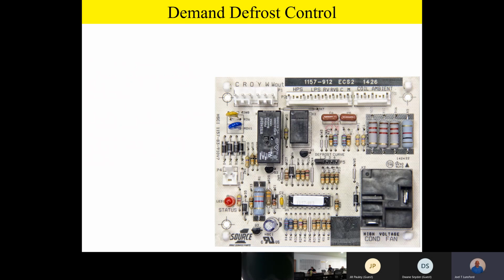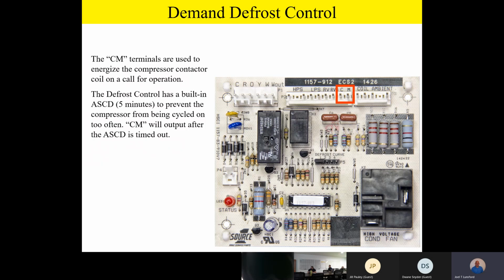Right next to that, you're going to have a couple of terminals called CM. Those CM terminals are outputs from the board down to the compressor contactor. And so we're going to bring the compressor contactor on with an output from the board on the CM terminals. Now, it should be noted, there's going to be a built-in 5-minute anti-short cycle delay. So the defrost control has a built-in anti-short cycle delay of 5 minutes to prevent the compressor from being cycled on and off too often. And so CM will output after that anti-short cycle delay is timed out.